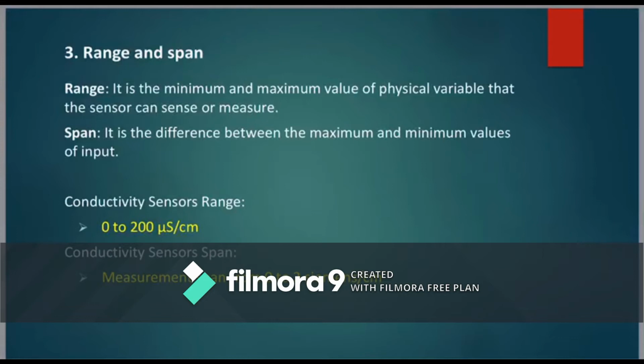For the conductivity sensor, the range covers 0 to 200 microsiemens per centimeter, and the measurement span covers from 0 to 2 Siemens per centimeter, and accuracy and non-linearity error.